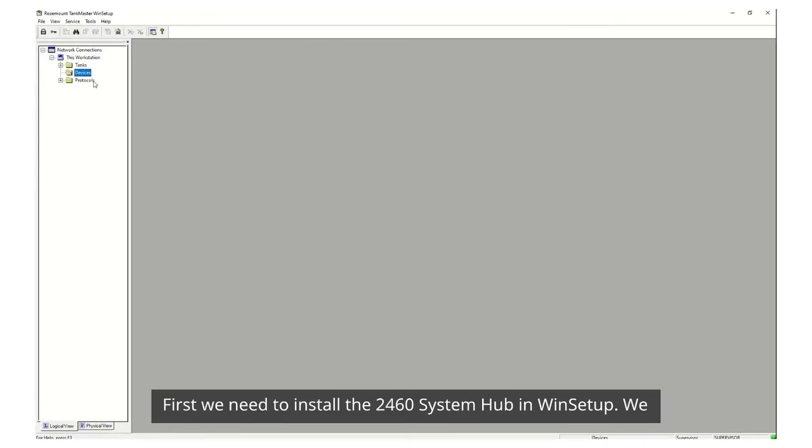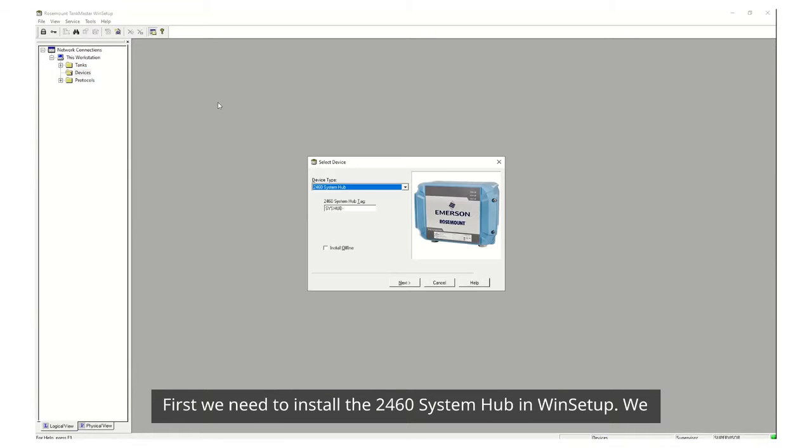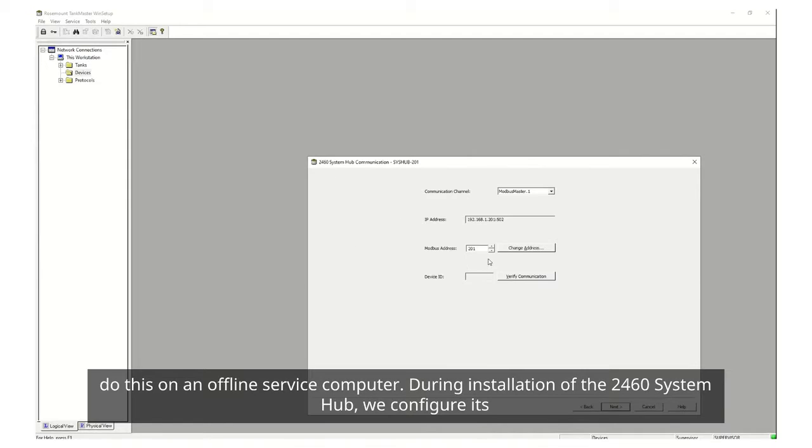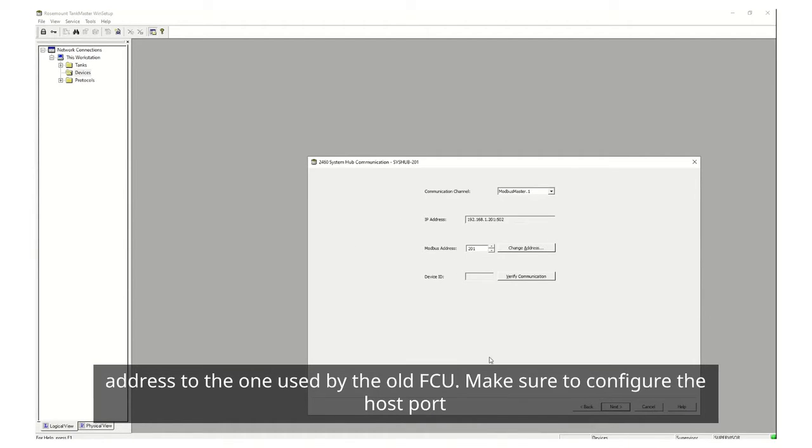First we need to install the 2460 system hub in WinSetup. We do this on an offline service computer. During installation of the 2460 system hub we configure its address to the one used by the old FCU.